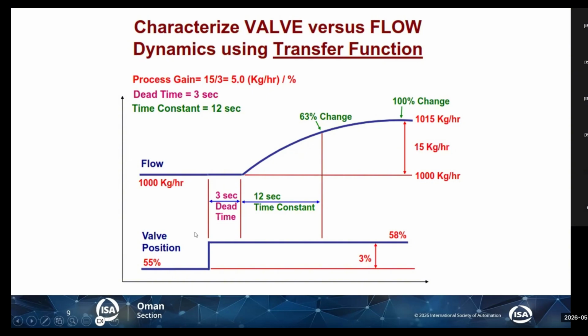I do a step test. Step test means I increased the valve opening from 55 to 58. So this will be the effect on the flow. It will increase gradually. Of course, if it is well tuned, it will increase gradually to reach the desired value.